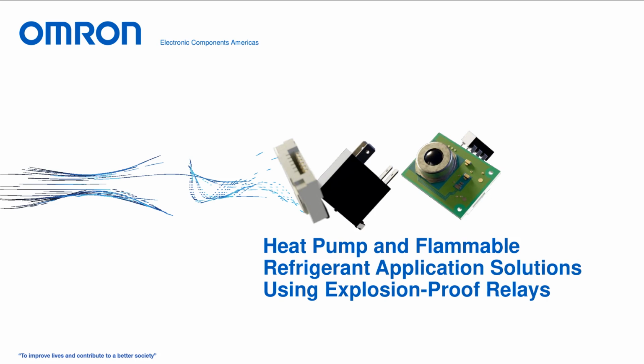And this means that we've done the testing through IEC to show that we will not ignite based on switching in these flammable gas environments. So even without that full barrier and that full isolation, we will not cause ignition of the flammable gases that were used within. So if there's a particular gas that you're concerned about, we can reference that particular IEC certification. But unsealed is definitely a go as long as we have the testing and the approval by IEC or UL. Okay, yeah, that's helpful.